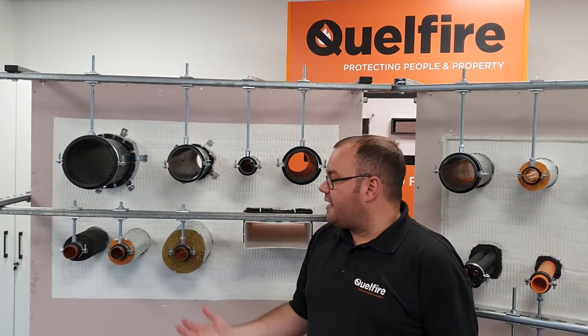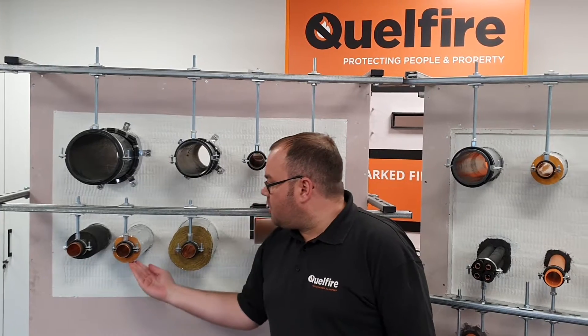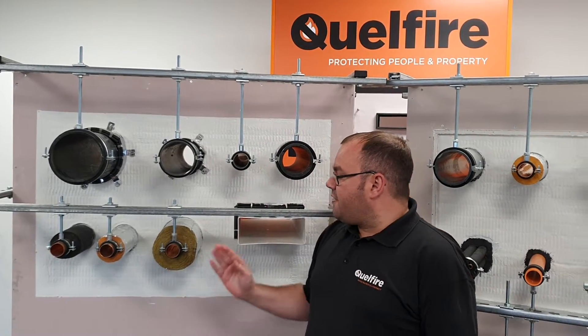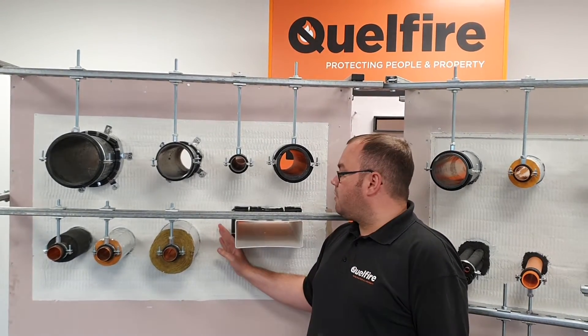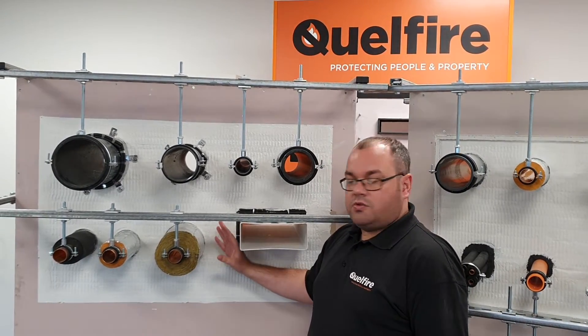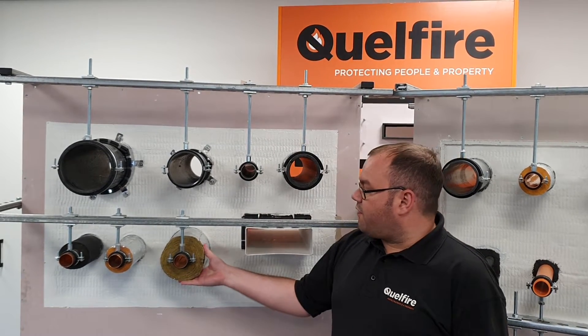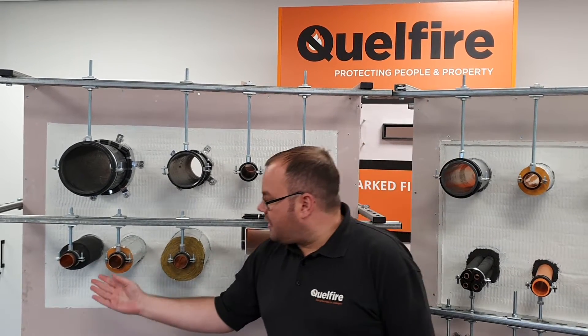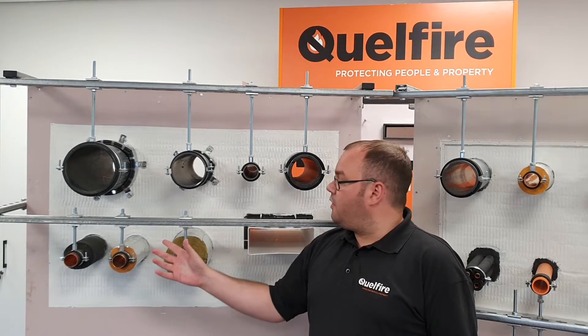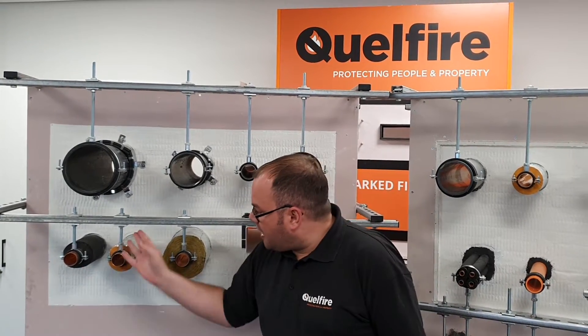If you're going to use insulation, there are a few options. Here we have examples of three commonly used insulations going continuously through the wall — straight through the fire batt or wall directly. We have ArmaFlex, Kingspan Kooltherm, and a rock fibre insulation. These are typically sealed using our Quelcoil intumescent wrap, with two layers around the insulation, as seen here.